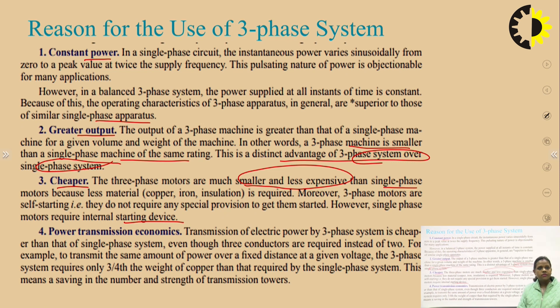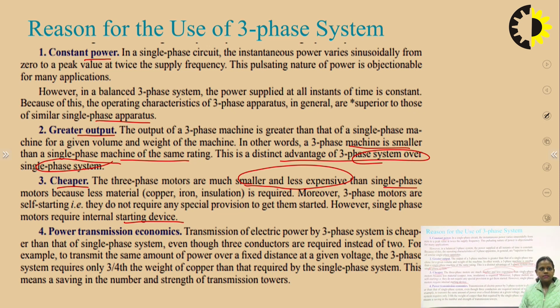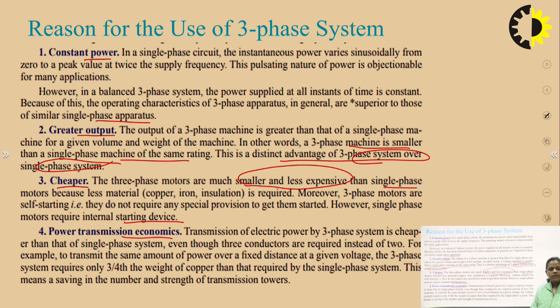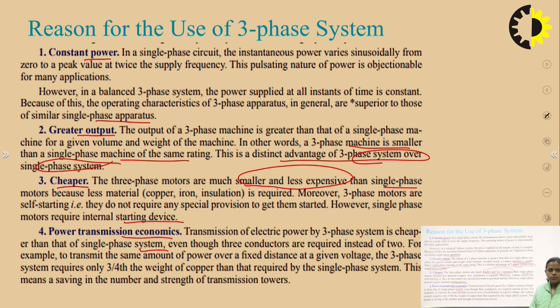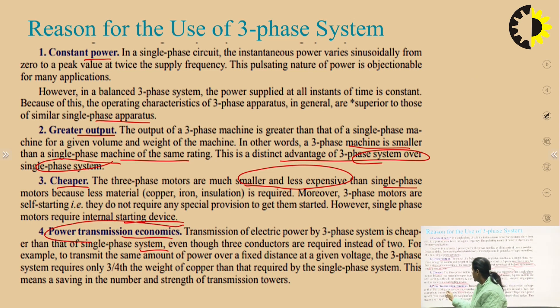Three-phase motors are self-starting — they do not require any special provision to start, whereas single-phase motors require internal starting devices. Another advantage is power transmission economics: transmission of electric power by three-phase system is cheaper than single-phase, requiring only three-fourths the weight of copper for the same power over the same distance, resulting in savings in the number and strength of transmission towers.